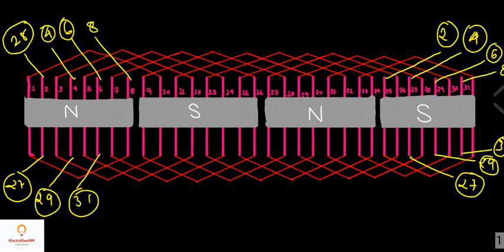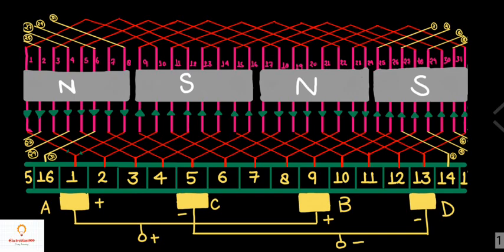Conductor 31 is connected to conductor 8, which is connected back to 1, completing our winding diagram of the lap winding. This is the complete winding diagram including the commutator bars. The pole pitch equals 8, so one pole covers 8 conductors. The next question is where to place the brushes — brush positions can be located by finding the direction of current in the various conductors.